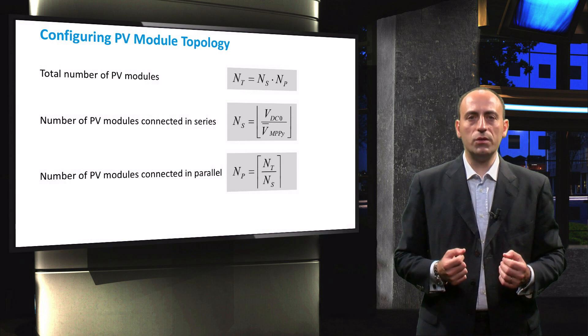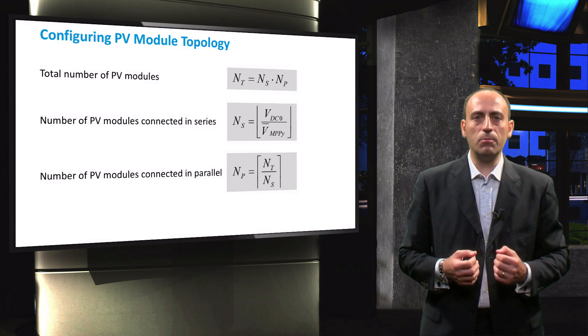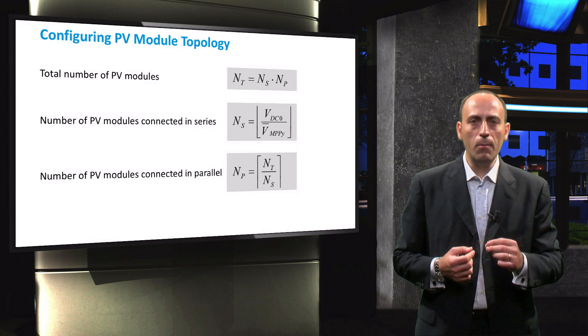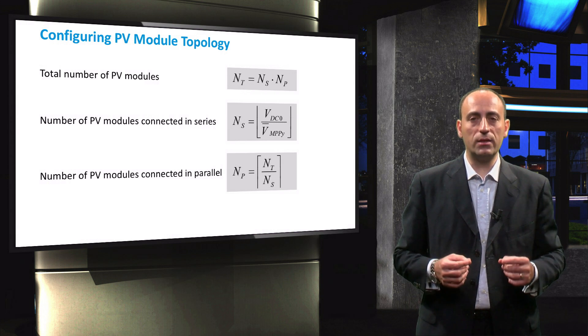Dividing the nominal DC voltage of the inverter by the averaged maximum power point voltage of the PV modules, we find the number of modules that should be series connected in a string.